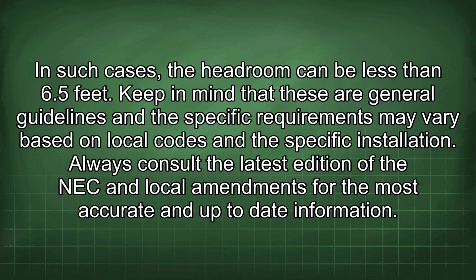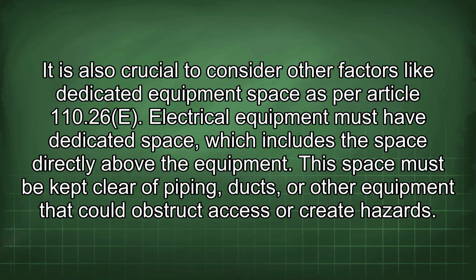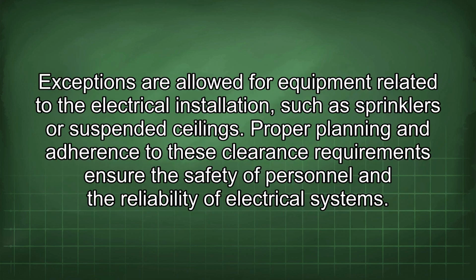Keep in mind that these are general guidelines and the specific requirements may vary based on local codes and the specific installation. Always consult the latest edition of the NEC and local amendments for the most accurate and up-to-date information. It is also crucial to consider other factors like dedicated equipment space as per Article 110.26(E). Electrical equipment must have dedicated space, which includes the space directly above the equipment. This space must be kept clear of piping, ducts, or other equipment that could obstruct access or create hazards. Exceptions are allowed for equipment related to the electrical installation, such as sprinklers or suspended ceilings.